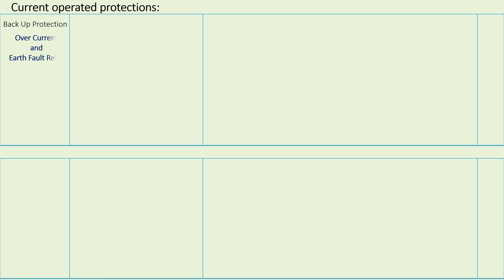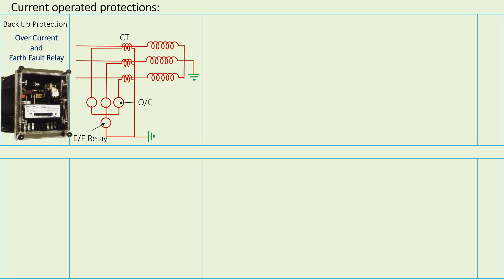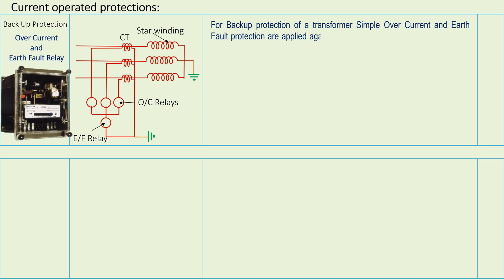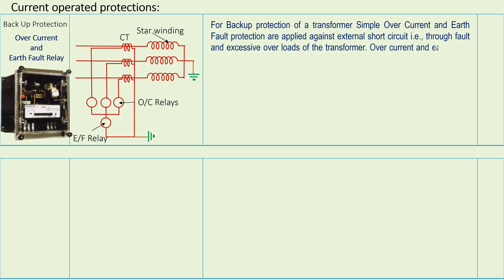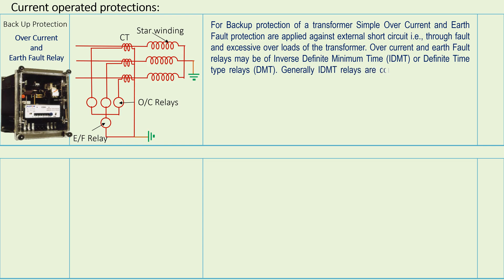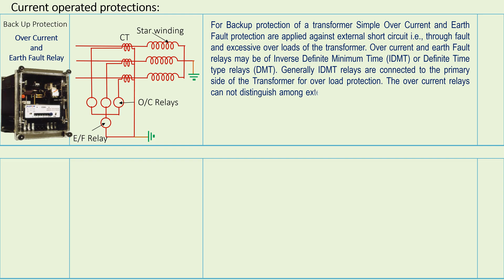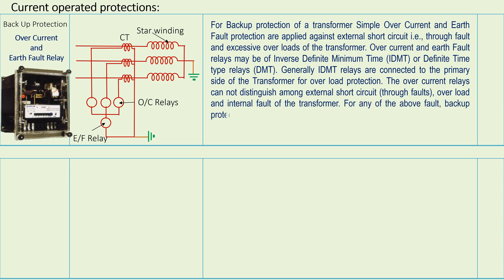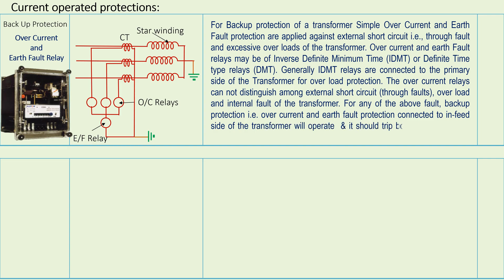Overcurrent and Earth Fault Protection: For backup protection of the transformer, simple overcurrent and earth fault protections are applied against external short circuit (through fault) and excessive overloads. Overcurrent and earth fault relays may be of Inverse Definite Minimum Time (IDMT) or Definite Time (DMT) type. Generally, IDMT relays are connected to the primary side of the transformer for overload protection. The overcurrent relays cannot distinguish among external circuit through faults, overload, and internal fault of the transformer. For any of these faults, backup protection connected to the input side of the transformer will operate and trip both the primary and secondary circuit breakers.